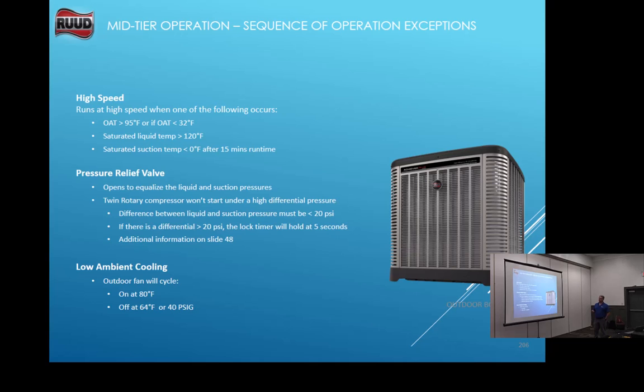We're going to talk about a pressure relief valve that's on the mid-tier systems because these units will not start if they have greater than a 20 psi pressure difference between suction and discharge. They will not start. Okay, and after 5 seconds, if it gets a call, it's going to check, and if it does, it'll open that solenoid to equalize the two lines, and I'll show you in another picture.